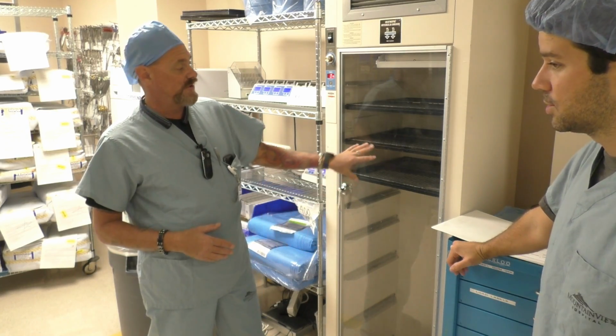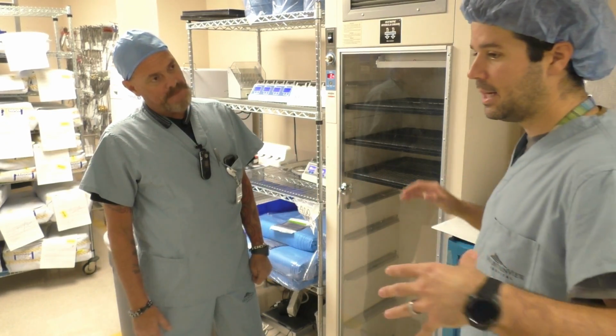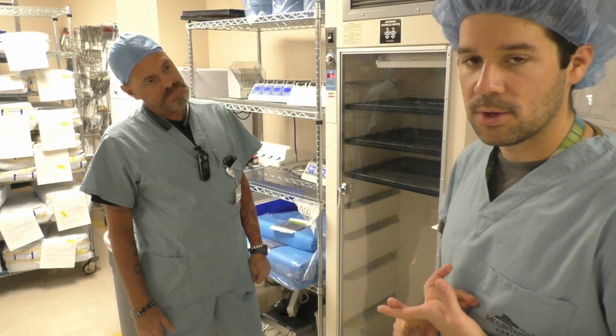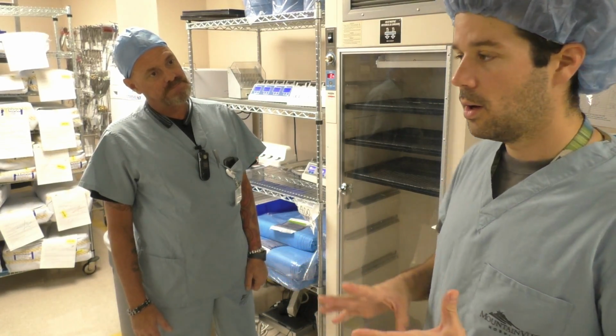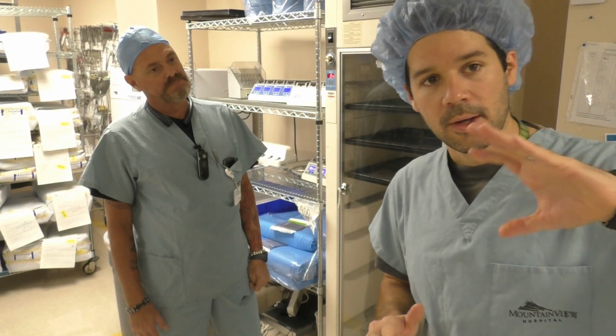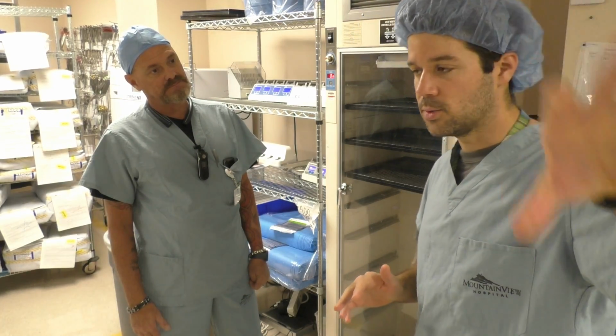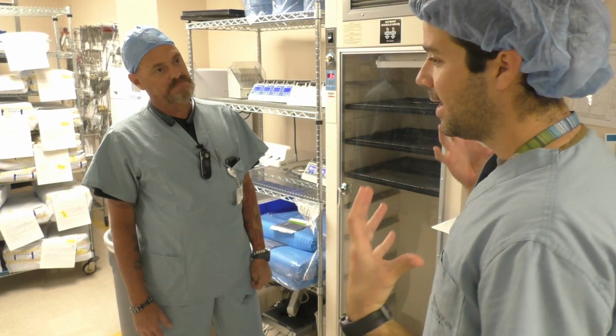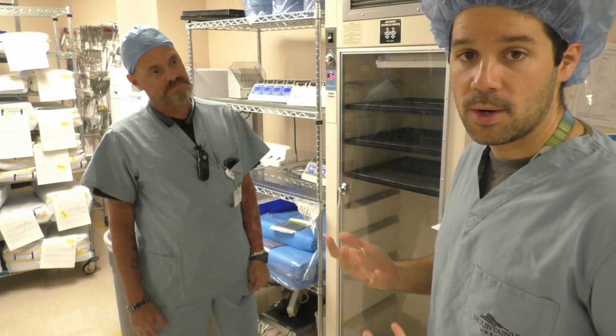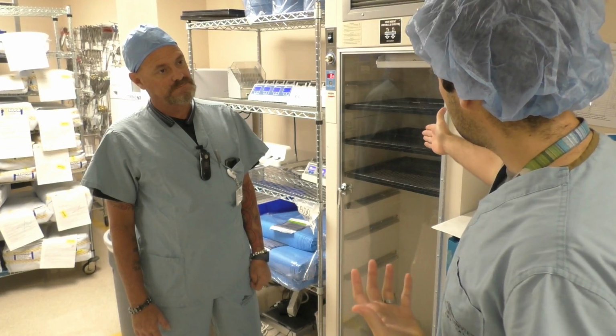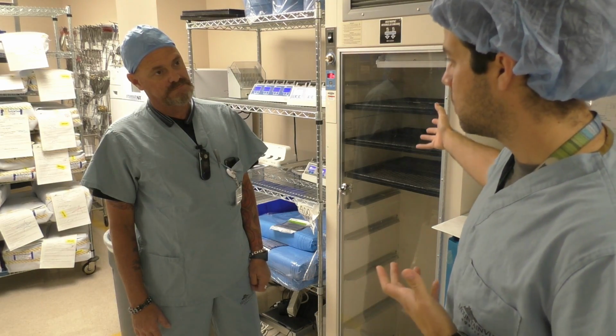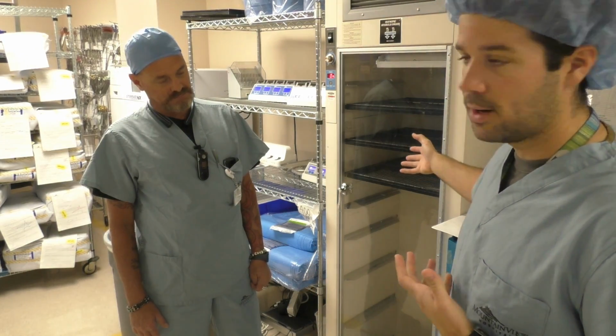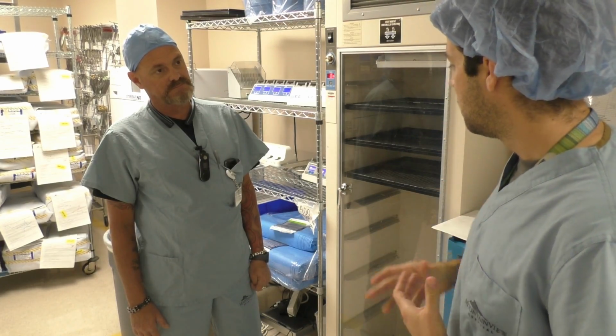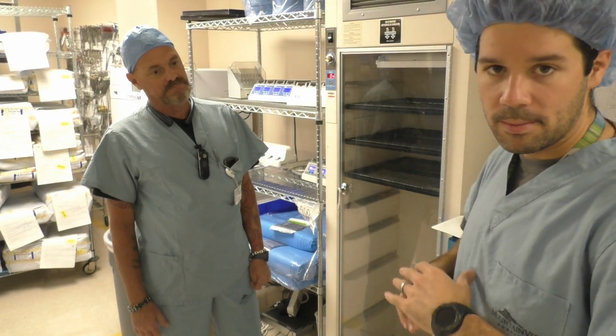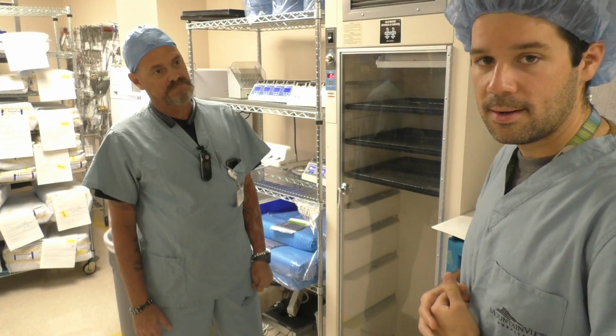Okay. So it goes in here and sits. Basically that means, let's say we have a laparoscope camera or a camera and light cord come down. It goes through the washer, it gets washed, it comes out here. It can't immediately go into the Sterrad because it's got moisture on it from the washer. So what he's saying is basically we have to put these light cords and camera cords in this dryer here to fully dry them before we box them back up, wrap them up, and place them in the Sterrad. Yep.